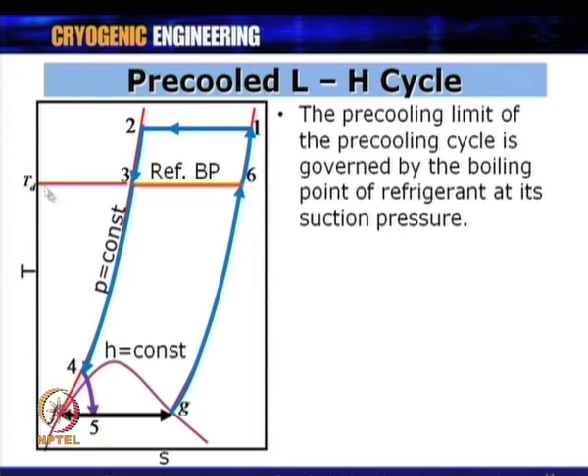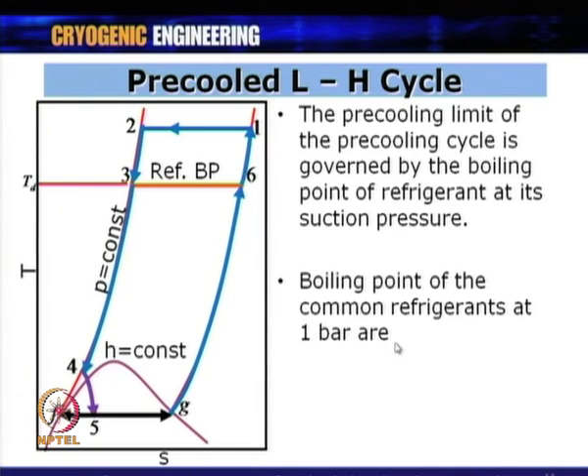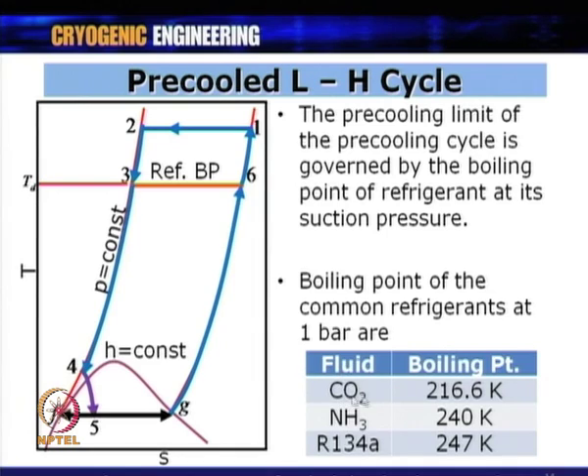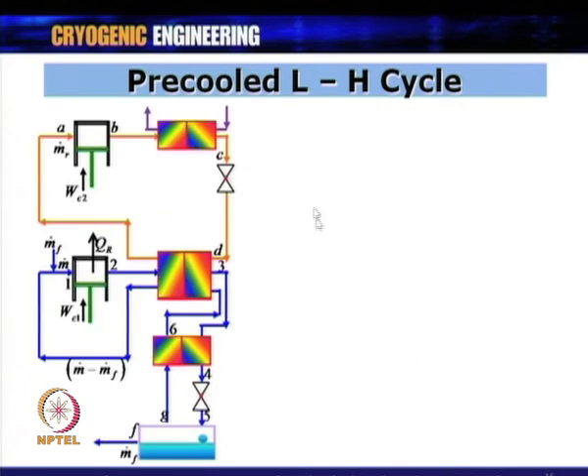The temperature Td at which the gas enters the heat exchanger equals the boiling point of the refrigerant at the suction pressure of the pre-cooling compressor. If the suction pressure is around 1 bar, these are the lowest temperatures achievable in the pre-cooling circuit. With these conditions, the gas enters the heat exchanger at this lowest temperature.